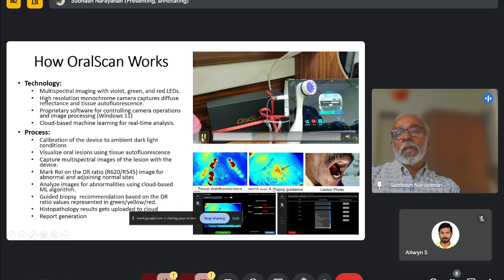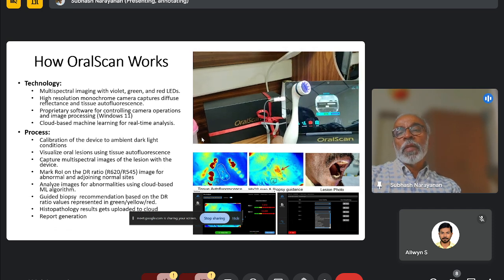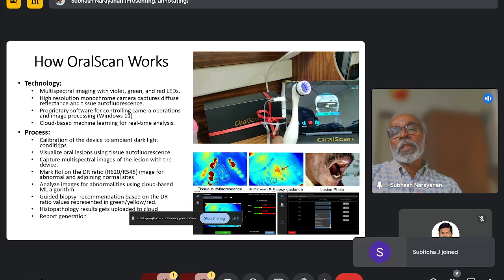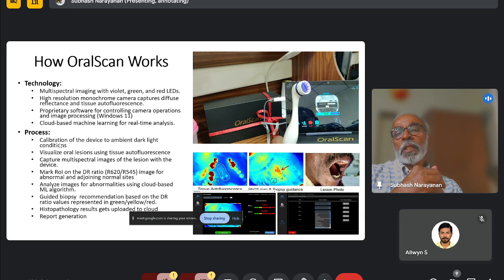You can see that with one click of the switch, all the LEDs fire sequentially, and with each firing, you capture an image. So we have three monochrome images captured on excitation with the violet, green, and red LEDs in around 1 to 2 seconds. This fast capturing will avoid patient movement and camera shake, so that registration of the images during the image processing becomes much easier. And we have a cloud-based machine learning algorithm which will provide the user feedback on the tissue status in real time.